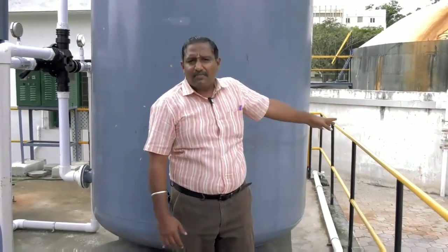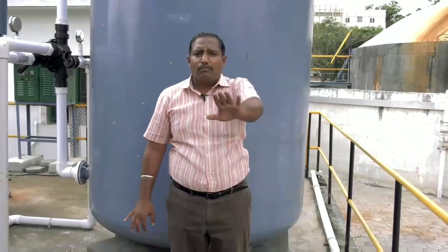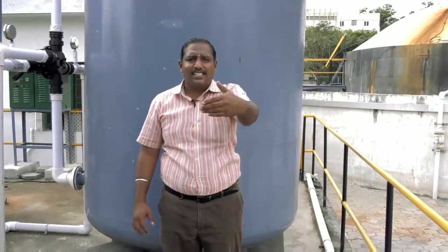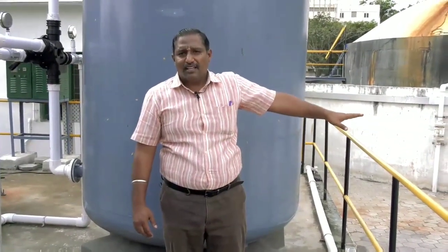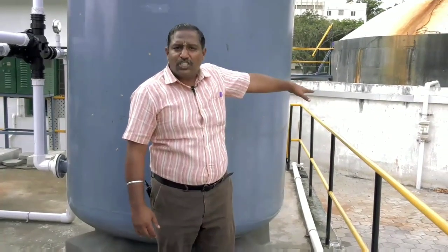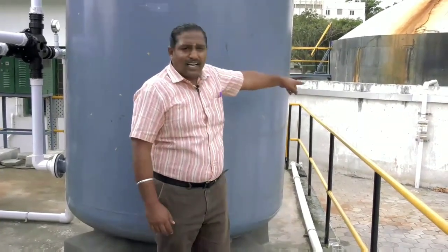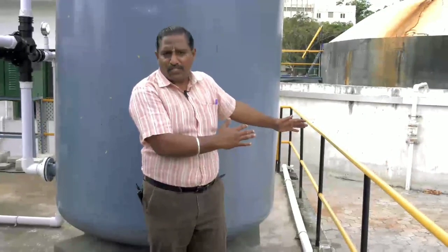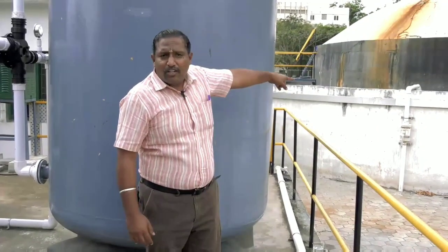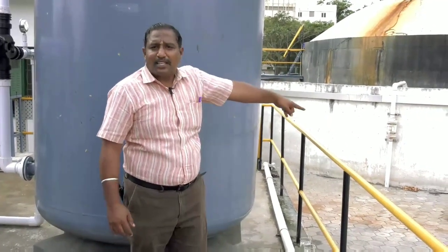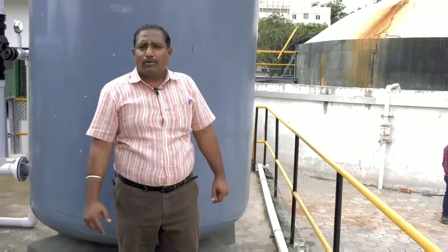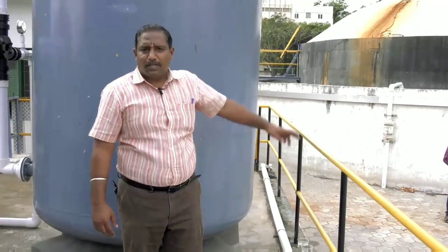In case of sewage treatment, as I have already told, we need not go for primary treatment or chemical treatment, which means unnecessary dumping of chemicals and results in huge generation of chemical sludge. That is not needed. So we are directly going for the biological treatment or secondary treatment. As I mentioned, it is a combination of both anaerobic as well as aerobic processes. First it enters the anaerobic chamber, where some pollutants are removed, and after which it enters the aerobic chamber, where more BOD and other pollutants and suspended impurities are removed.